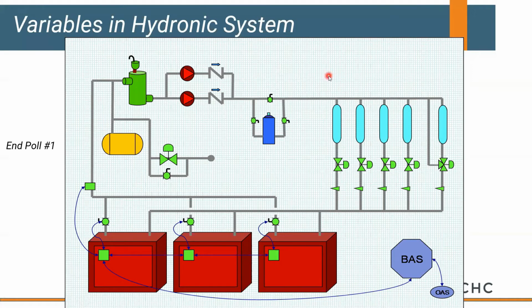What advantages are inherent with a high turn down boiler? Less cycling. That's absolutely true. High turn down means we're not going to cycle our equipment as much, so that's an advantage. Longer lifespan on our blower and electrical components. Improved ability to track system diversity. Absolutely, this is a big one as well. There's a lot of changes in our system. I'll talk about that in just a minute.